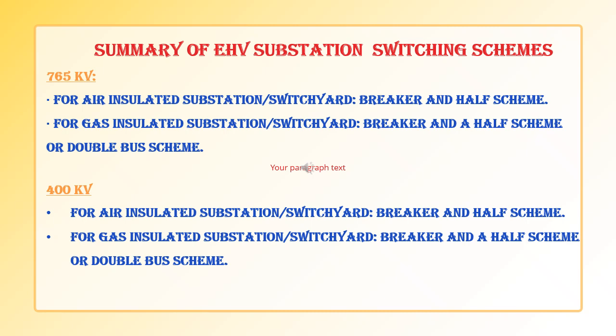Summary of EHV substation schemes. For 765 kV, the breaker and half scheme is used for an AIS substation. The breaker and half scheme or double bus scheme is used for a GIS substation. For 400 kV, the breaker and half scheme is used for an AIS substation. The breaker and half scheme or double bus scheme is used for a GIS substation.